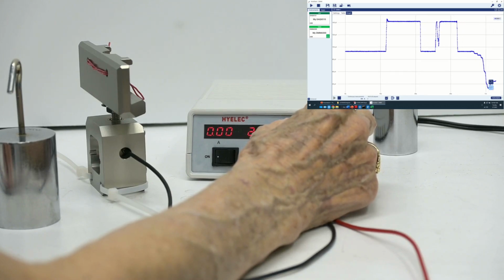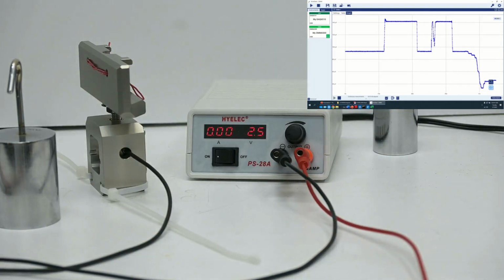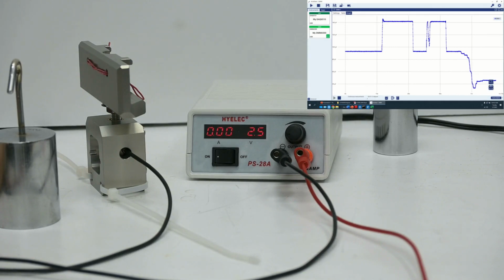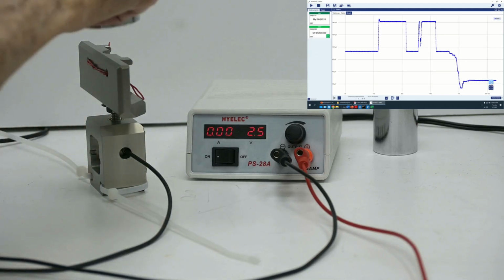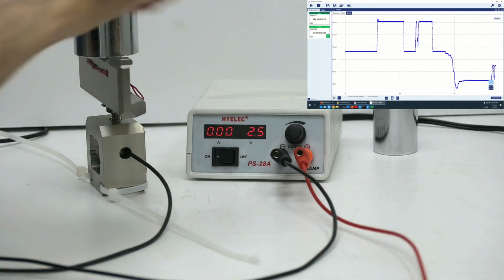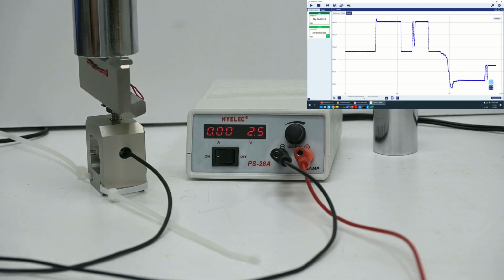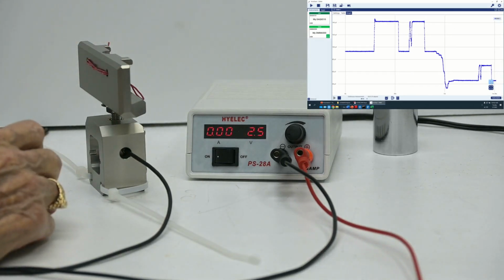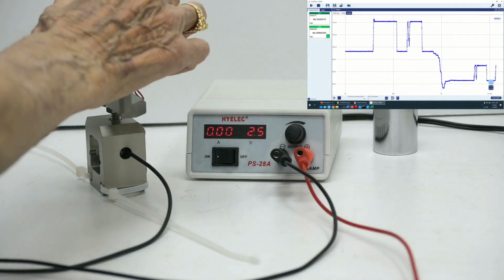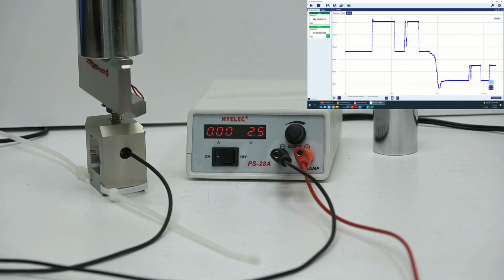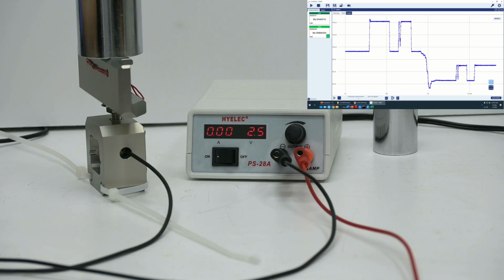Note that the no-load voltage has changed to 45 or 46 microvolts. With the 1 kilogram load, it is about 70 microvolts. Off, 45 microvolts. On again, 70 microvolts. The change is 25 microvolts. The sensitivity is about 25 microvolts per kilogram, as compared with 46 microvolts per kilogram in our test using the Keithley 5-volt supply. Keep that in mind. If the power supply changes, you need a new calibration.